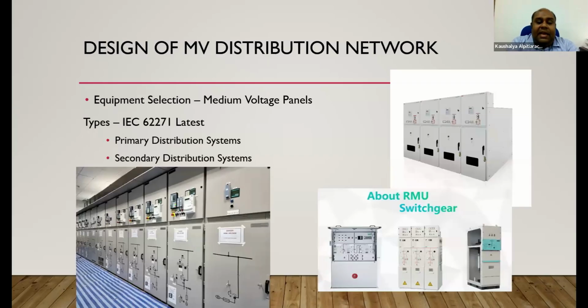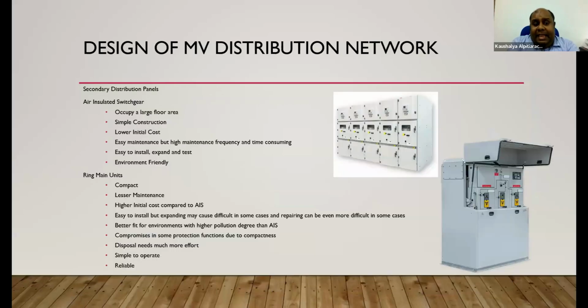Equipment selection, medium voltage panels. The standard is IEC 62271, the latest edition. You have two options: primary distribution systems and secondary distribution systems. Since we are discussing MV distribution systems in buildings, we'll stick to secondary distribution systems. There can be two options: air insulated switchgear or ring main units.